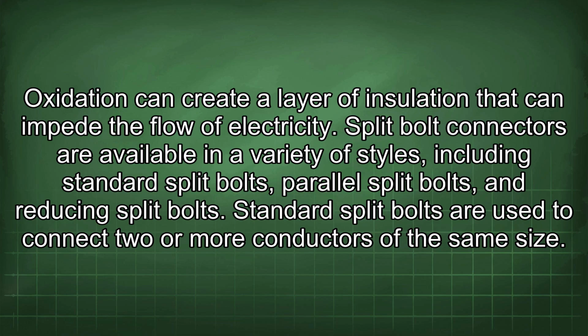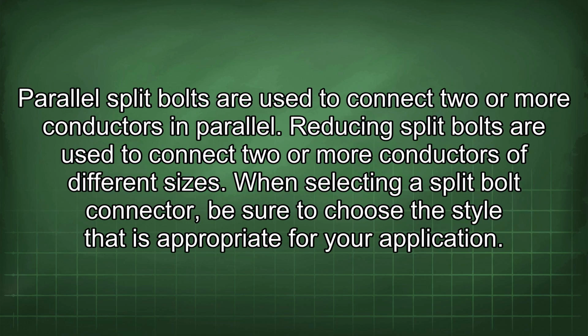Split bolt connectors are available in a variety of styles, including standard split bolts, parallel split bolts, and reducing split bolts. Standard split bolts are used to connect two or more conductors of the same size. Parallel split bolts are used to connect two or more conductors in parallel. Reducing split bolts are used to connect two or more conductors of different sizes. When selecting a split bolt connector, be sure to choose the style that is appropriate for your application.